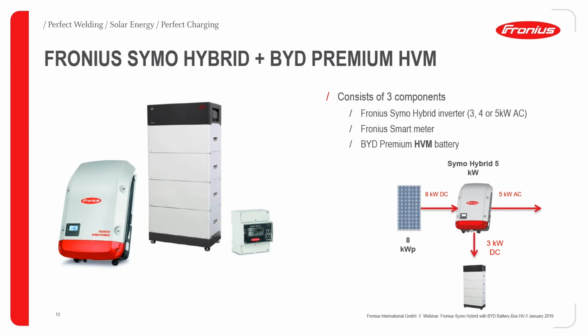So as you can see in the little diagram there, if you do have, let's say, 8 kilowatts of PV here, because of the MULTIFLOW technology, and we'll go through that a little bit in the next slide, you can have 8 kilowatts DC coming in and producing 5 kilowatts AC and 3 into the battery at the same time. Or let's say maybe 3 kilowatts AC and 5 into the battery, depending on what's going on.